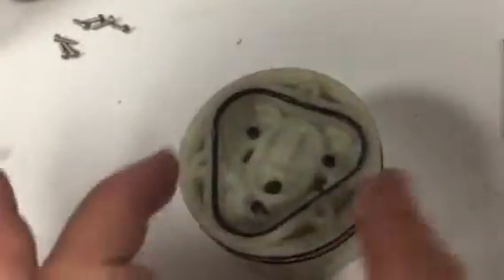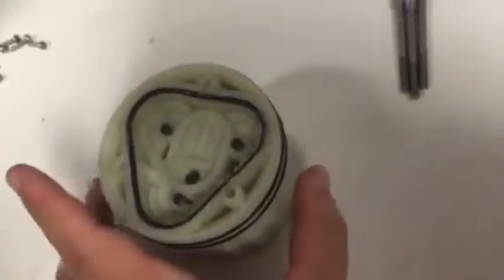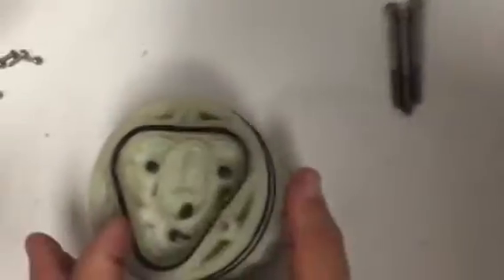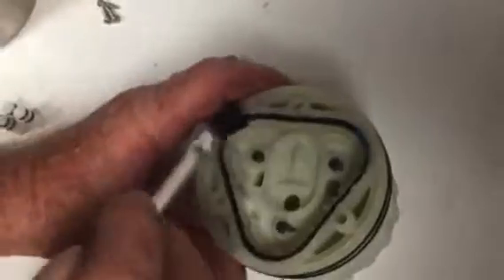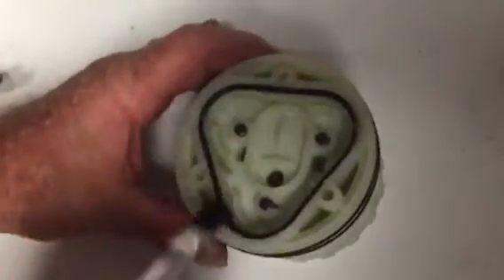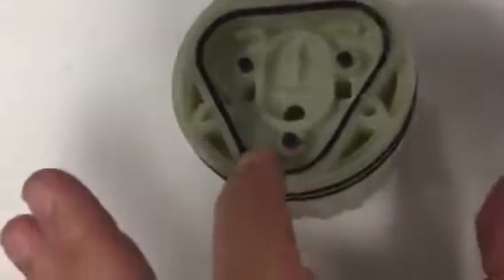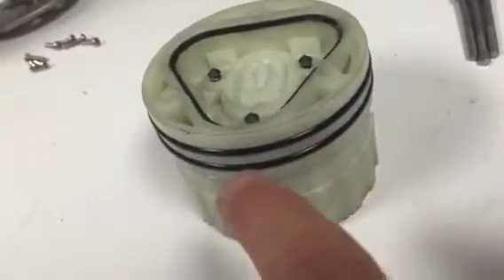Next, we will make sure that this O-ring, the internal sealing O-ring, stays in place. It's very important. As you're taking the pump head and putting it over on top of the motor, you want to make sure that that O-ring does not fall out to be pinched. So we take our Dow Corning 111 and we apply generously some lubricant on there. That will both lubricate and it will hold it into place, literally sticking it into the pump head assembly. We also have already applied some Dow Corning 111 on the outer sealing O-rings.